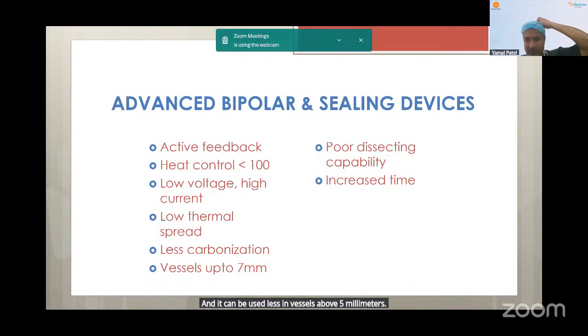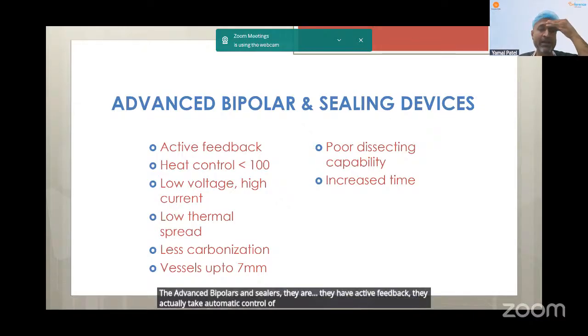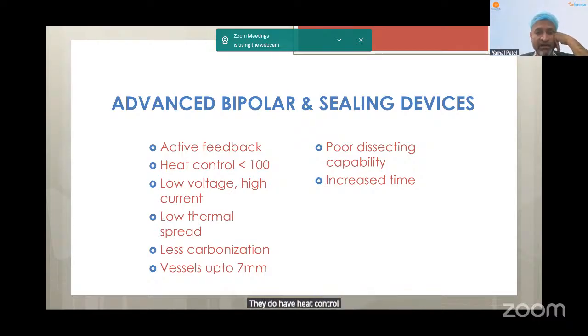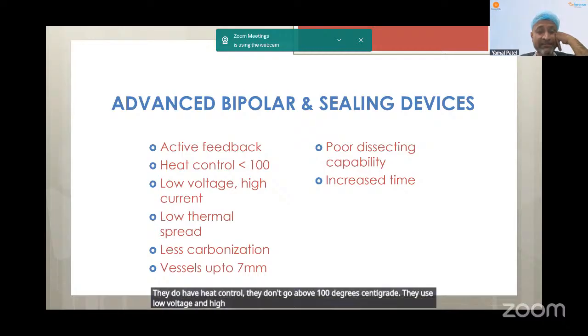The advanced bipolars and sealers have active feedback. They take automatic control of telling you when it is ready. They have heat control and don't go above 100 degrees centigrade. They use low voltage and high current, making it safe. They have very low thermal spread, less carbonization, and can easily seal vessels up to 7 millimeters. However, they are poor in dissection and slow in activity.